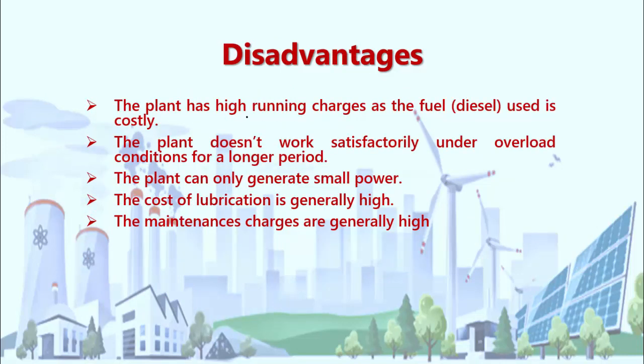There are very few disadvantages with this. The running charges of this power plant are high since the fuel used here is diesel. The cost of diesel is very high, so the unit charge of the electricity produced by the diesel power plant will also be higher. The plant does not work satisfactorily under overload conditions for a longer period. It will be a standby unit only. It can run for a shorter period only, right?